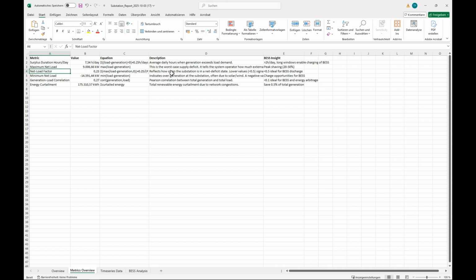We have a net load factor, which reflects how often the substation is in a net deficit state. Smaller than 0.5 is ideal for BESS installation. We have a minimum net load, meaning minimum load minus generation, so there is over generation at the substation, peaking here at 14.5 megawatt. So at a certain point in the last 12 months, 14.5 megawatt was injected into the grid, which are great charging opportunities for batteries to also help the grid not need to absorb so much power.